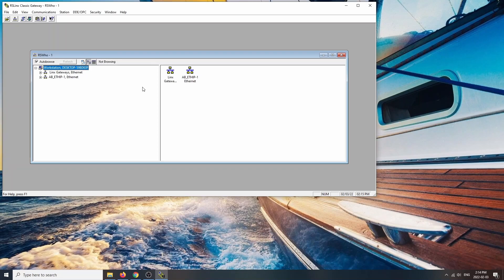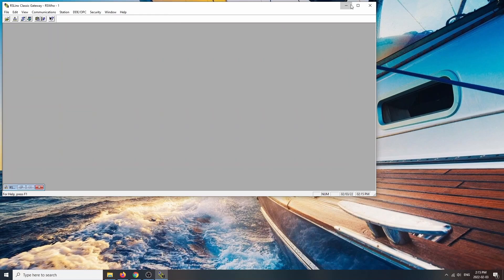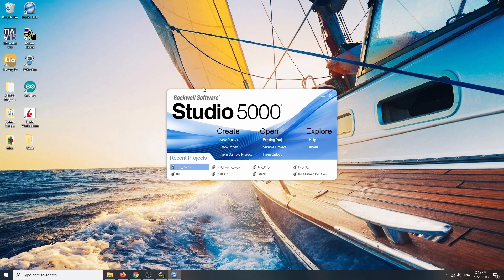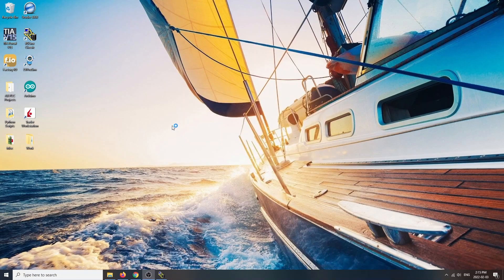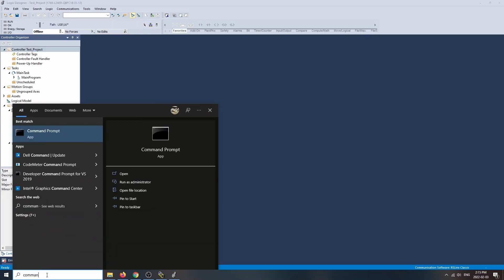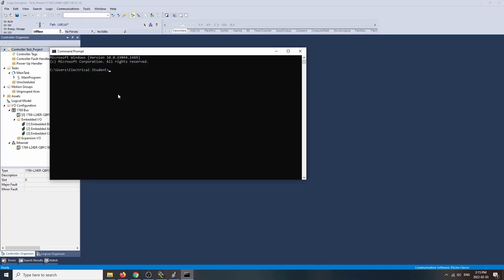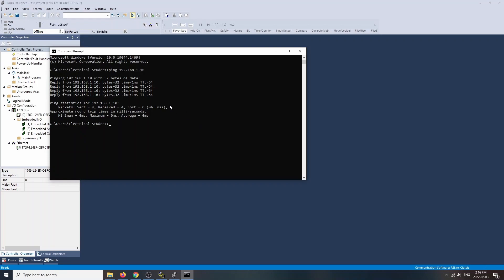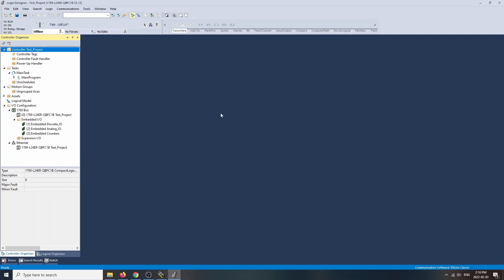Now open Studio 5000 and open the test project we were working on. If you want, you can open a command prompt and ping the PLC at 192.168.1.10 to verify the connection. It looks good — we're actually talking to the PLC. That step isn't required, but it's useful to confirm communication. Let's close the command prompt and go to Communications.